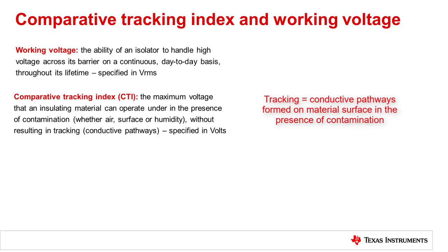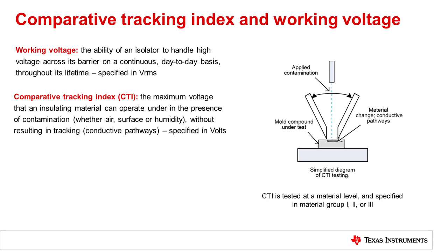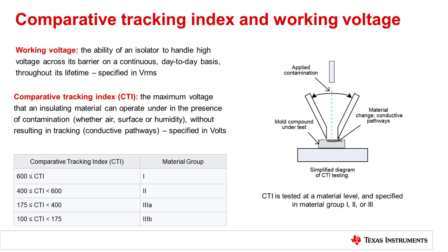Tracking is the creation of conductive pathways on the surface of an isolation material and is characterized through standardized material testing. If conductive paths are established on the surface of an isolator, the potential for arcing increases. For this reason, working voltage and package material level with a known CTI are directly related to end equipment creepage and clearance distance requirements.